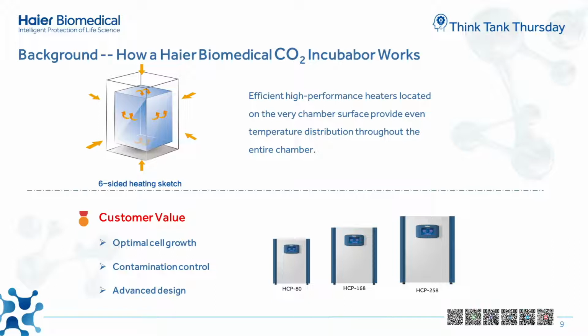Haier Biomedical incubators also provide faster recovery after door opening. This is due to the fact that an air jacket incubator can adjust the temperature on and off cycle based on the air temperature inside the chamber, following the door openings. Haier Biomedical incubators are also suitable for high heat sterilization at temperatures upwards of 180 degrees Celsius. This is something that is not possible when using water jacket models.